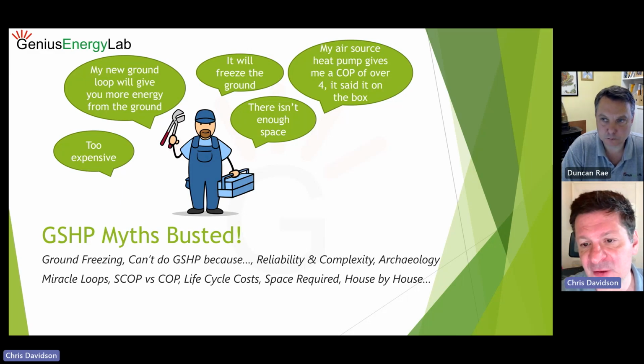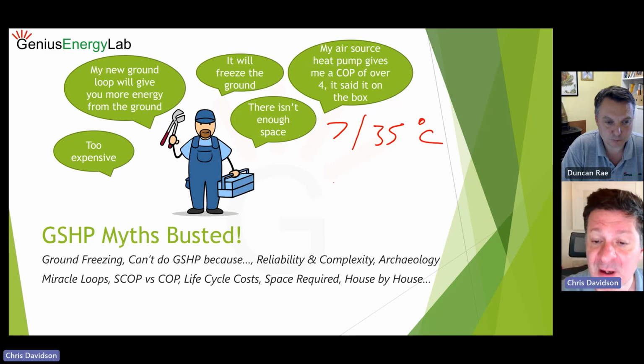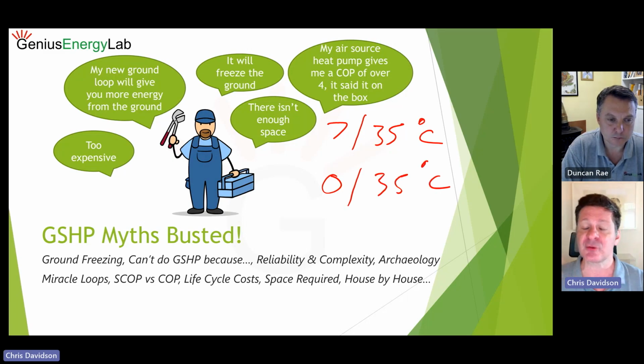So for example, for air source heat pumps, it's 7 degrees on the source and 35 degrees on the load. For ground source systems, 0 on the source and 35 on the load is the standard rating point. So back to my point there, the temperature difference between source and load is proportional to the electrical consumption. So electrical consumption goes up as we increase that temperature. It's not fair to compare a ground source standard rating point at 0 degrees 35 with the air source at 7 35. In order to do that properly, you need a seasonal coefficient of performance. So that's the annual heat delivered divided by the annual electrical consumption, so average throughout the year.